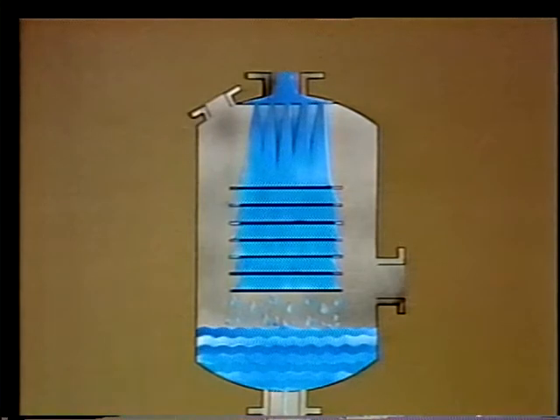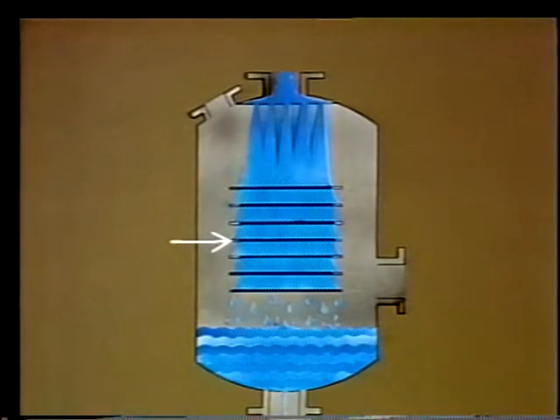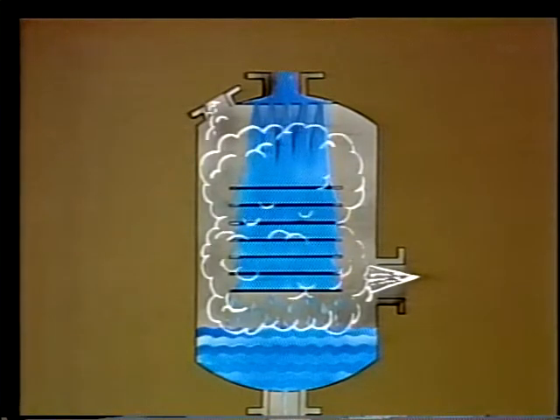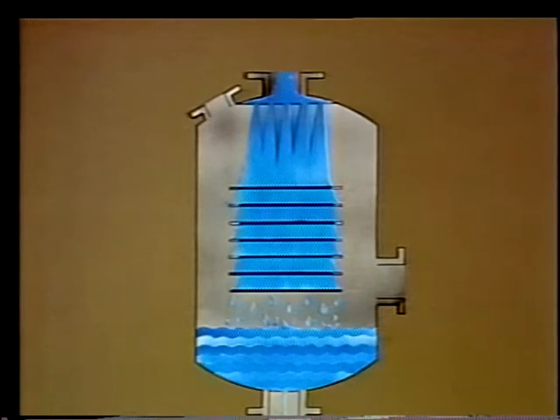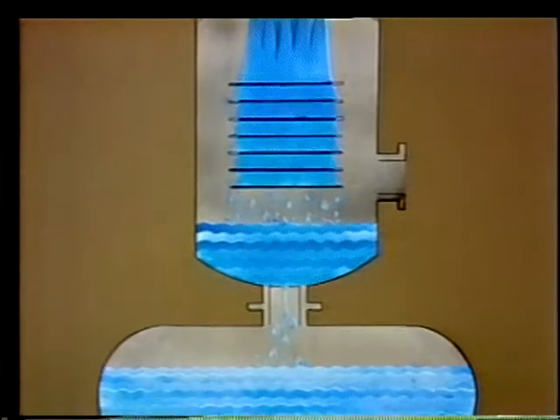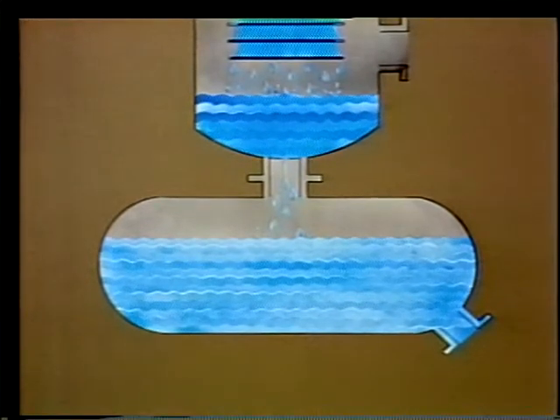Our third example is a more efficient unit because it combines both the spray and tray methods. Spray nozzles direct the incoming feed water down through the live steam coming up from the inlet. As it falls onto carefully positioned trays, it condenses some of the steam and is heated up. The condensed water from the steam joins the feed water as it flows down over the trays, and the water picks up even more heat as it falls past the hotter incoming steam. Direct contact heaters then drain the heated feed water and condensed steam either into a storage tank or it can be directly pumped into the boiler feed system.